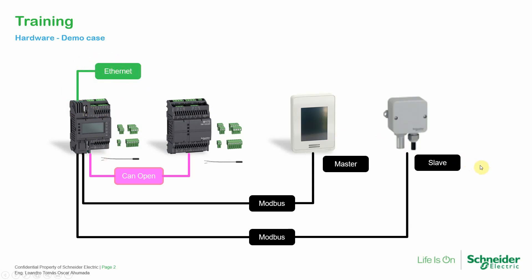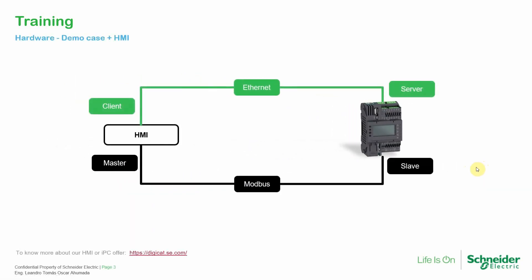What we're going to do with our demo case is use the Modbus port for the slave of the PLC to communicate to the HMI, where the HMI would be the master. Then for Ethernet communication we are going to use the HMI as a client and the PLC as a server.